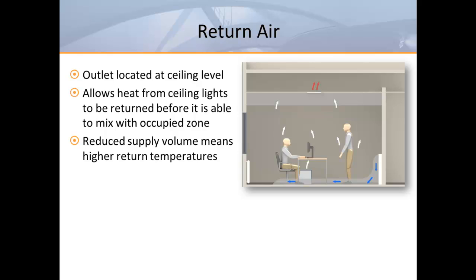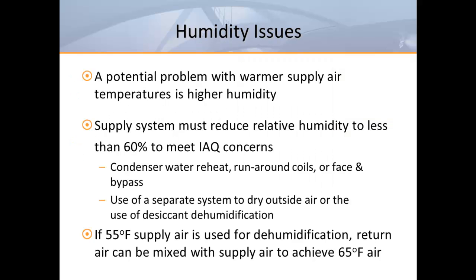In order for displacement ventilation to work most efficiently, the return air should be pulled from well above the occupied zone, preferably from the highest point in the room. Since much of the heat load from overhead lighting is captured above the occupied zone and supply temperatures are higher, you should expect higher return air temperatures than in a conventional mixed air system. To avoid potential humidity issues and air quality concerns, we need to limit relative humidity to 60% or less. There are many strategies we can employ at the air handler, or we might choose desiccant dehumidification. If we choose to drop our air temperatures to 55 degrees to wring the moisture out of the air, we can blend return air with the supply air to bring it back to 65 degrees.